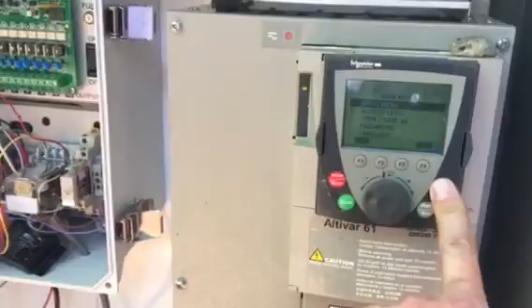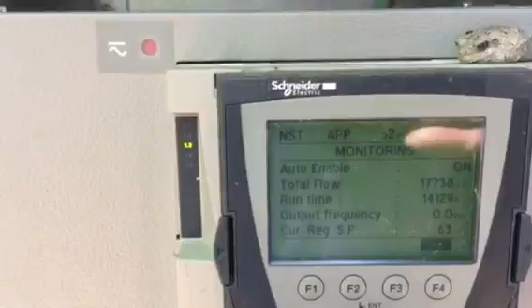But what we have here is, you can see, no start. It's running the application, which is a pump. We're at 62 psi and 0 GPM. This thing's moved 17 million gallons so far, and it's got a runtime of 14,000 hours.